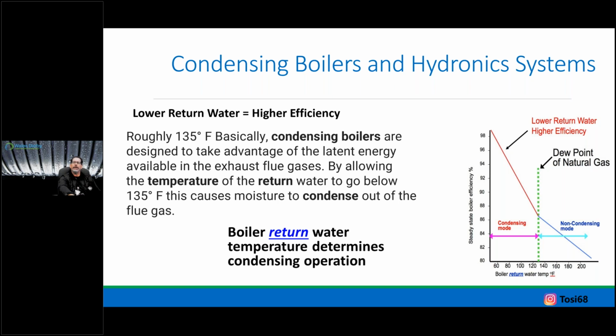If we had to be something higher, yeah, we can be at certain portions of our heating season. So you think about how often it's a design day of 10 degrees outside, it's really small. So it's okay if the boiler needs to operate there, but for the amount of runtime or firing throughout the season, how many hours of operation, if I'm mostly to all the time on the condensing side of that graph, that's when we know we're winning. That's when we see the neutralizer wet. That's when we see we have a trickle of condensate that's been neutralized and sent down the drain.